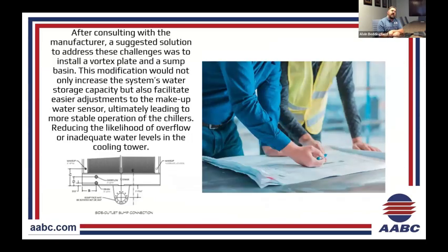So reaching back out to them, they said, hey, the easiest thing is to add the sump, and it's going to add a little bit of capacity at the bottom. The pump's going to pull from it, which allowed us to really adjust that makeup water correctly and allow those pumps to pull from that sump basin rather than the side. Because at this point, obviously the sump's at the lowest point, so you're not going to be able to pull air anymore. And once we got the operating level, we were able to set the autofill onto that valve and really establish that.